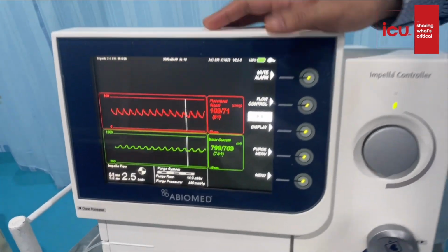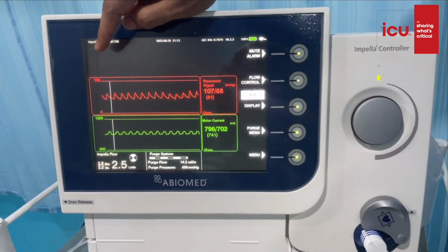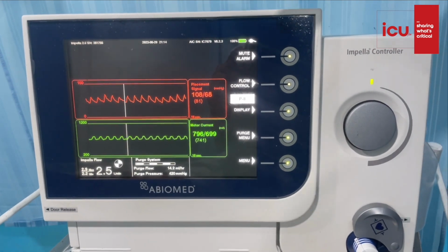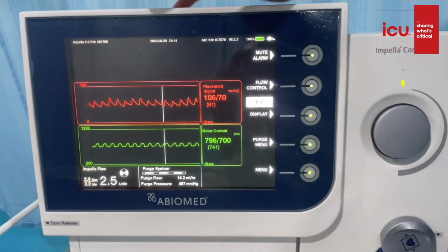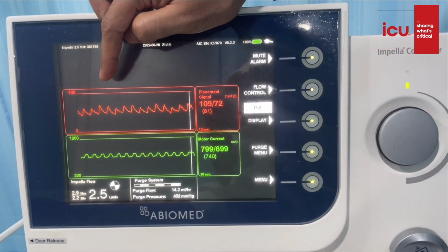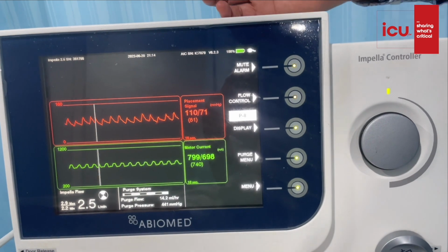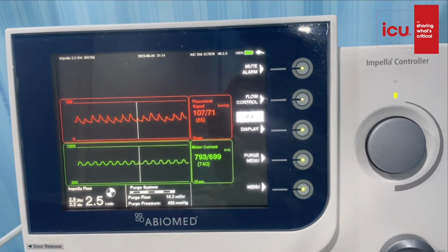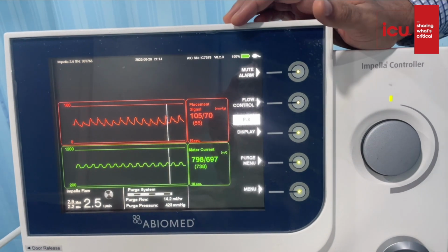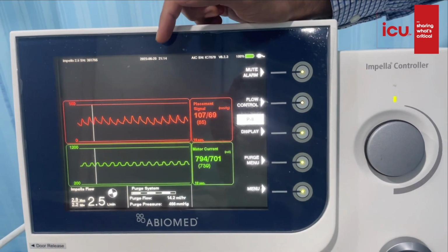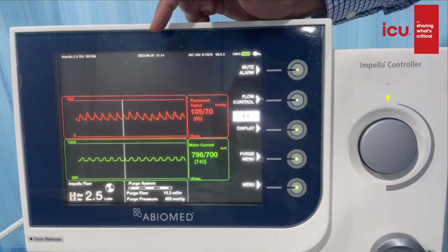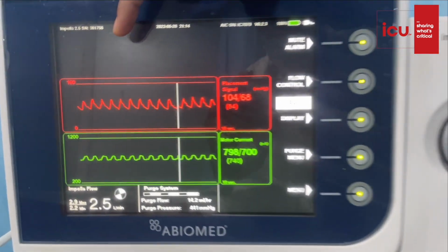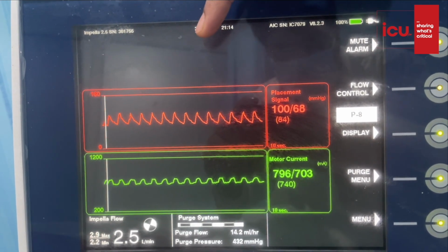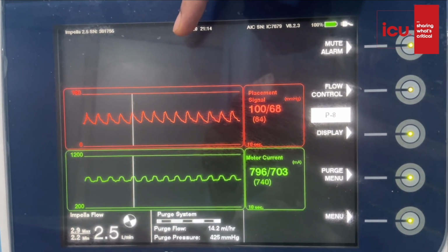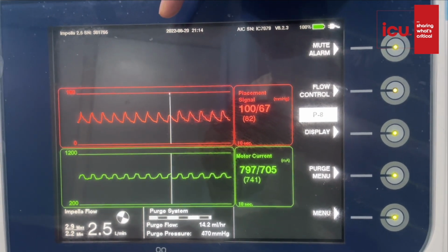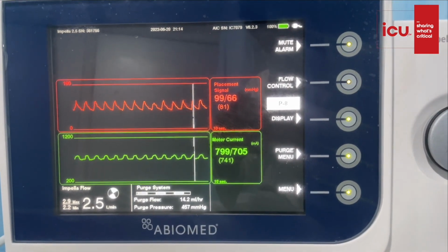So this console monitor, first we'll go from top to bottom. First, on the top you will see a red color waveform. This we call a placement signal. The placement signal is nothing but your aortic pressure waveform, and this is produced with a pressure transducer which is located just proximal to the motor housing unit of the Impella catheter. This also helps you to understand the right position of the device. In normal circumstances this should always be an aortic waveform. If you see a very tall ventricular waveform, it indicates that your Impella device is too deep seated into the LV. So in that situation you have to pull the device back.